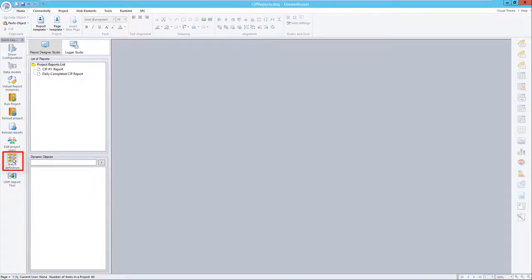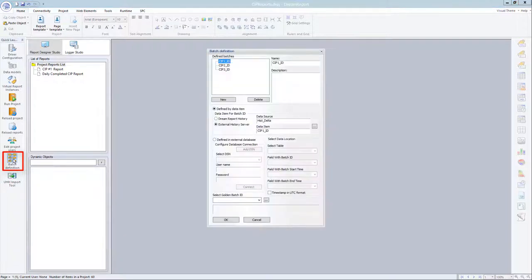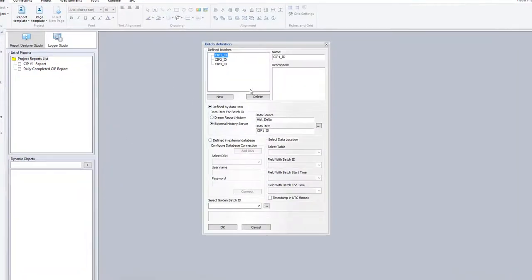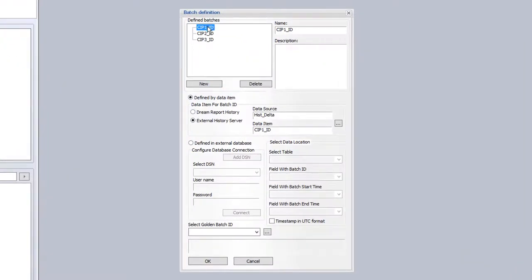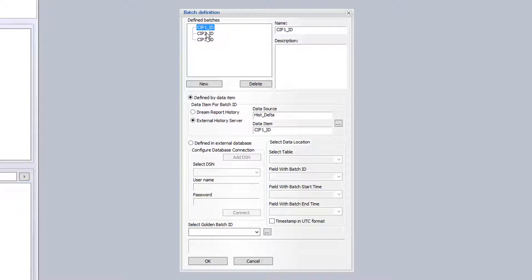Once the communication driver is configured, we now use the DreamReport batch definition module to define a batch, or in our case a CIP ID, for each unit. In my example, I have three mixing tanks, each having its own unique tag for the CIP ID. As such, I create the batch IDs in DreamReport, pointing to each tag respectively.